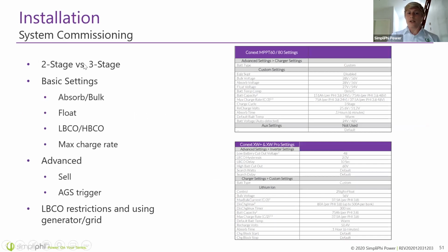When you're commissioning the system, here's some programming to go over. 2-stage charging is great for an AC power source like the grid or a generator. One important thing: you don't want your generator hanging around running just to float the batteries—that's a total waste of fuel, and you'll end up with angry customers if you forget about that.